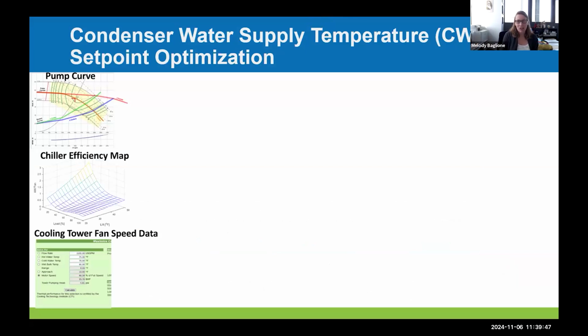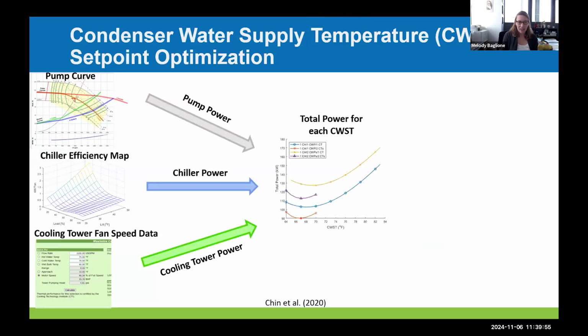Essentially, the students took pump curve data from the manufacturer, chiller efficiency map, and cooling tower data, and did a parametric study considering pump, chiller, and cooling tower power. They then used building management system actual data to also validate the manufacturer data.